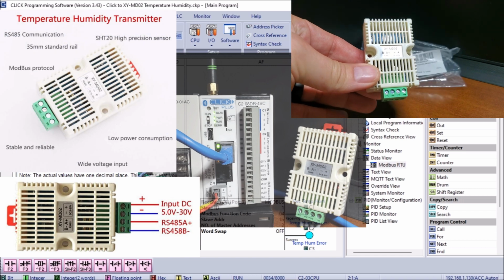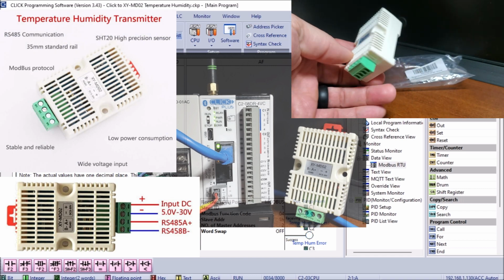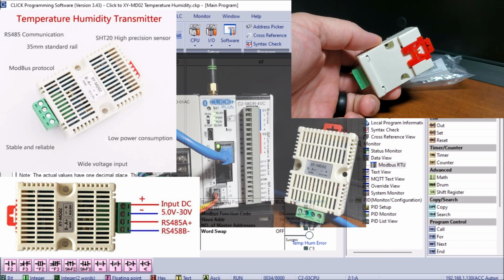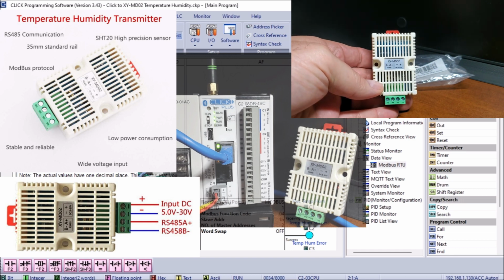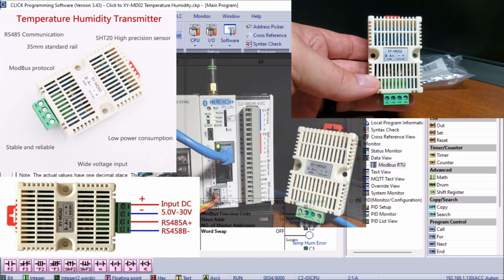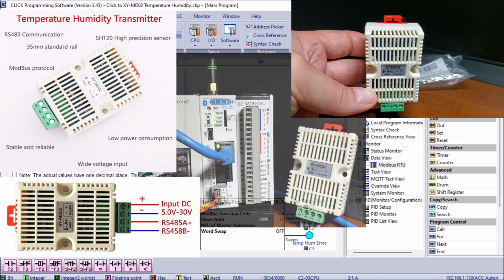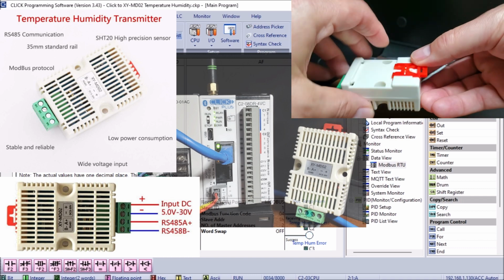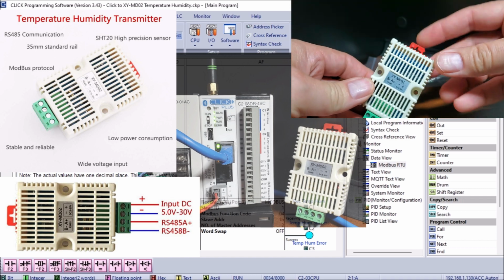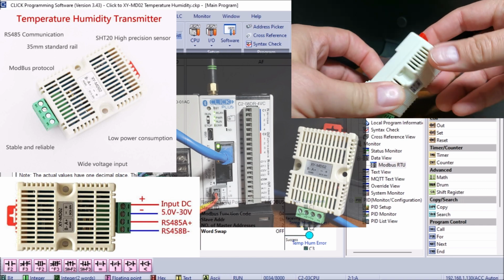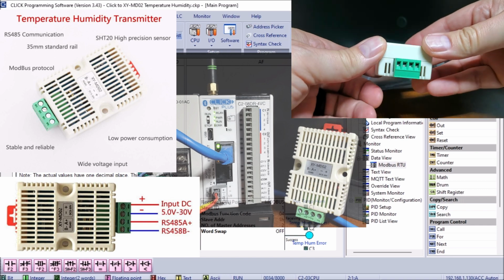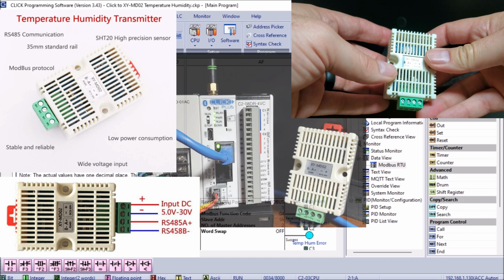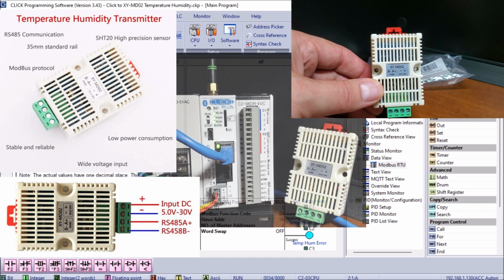This is an ideal sensor to place in a panel to ensure that the panel is within operating temperature and humidity range. The XY-MD02 is an industrial Modbus RTU device that reads temperature and humidity. We will create a PLC click program that will read the temperature and humidity from the sensor. We will also read the parameters from the sensor like unit number, baud rate, temperature offset, and humidity offset.